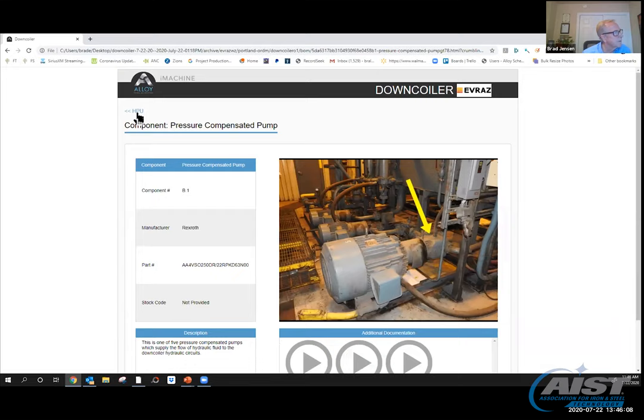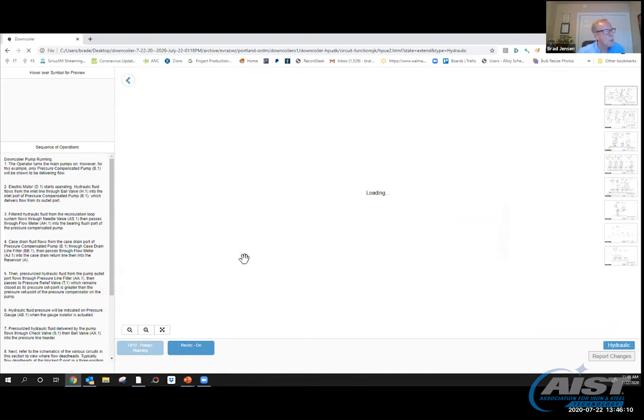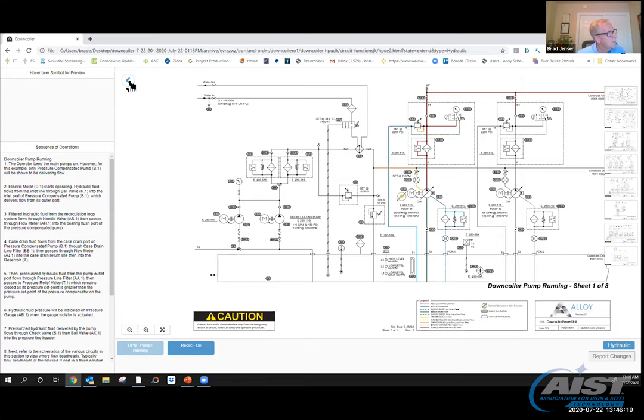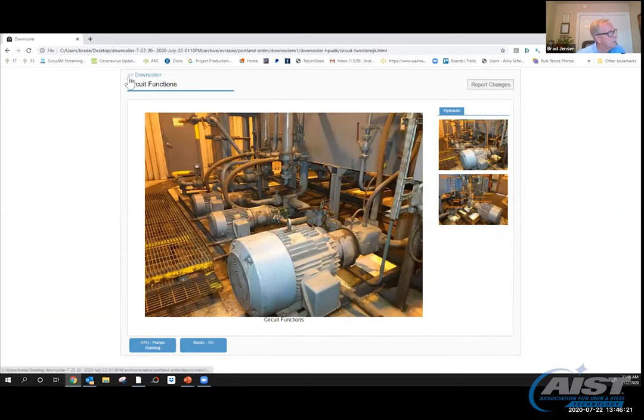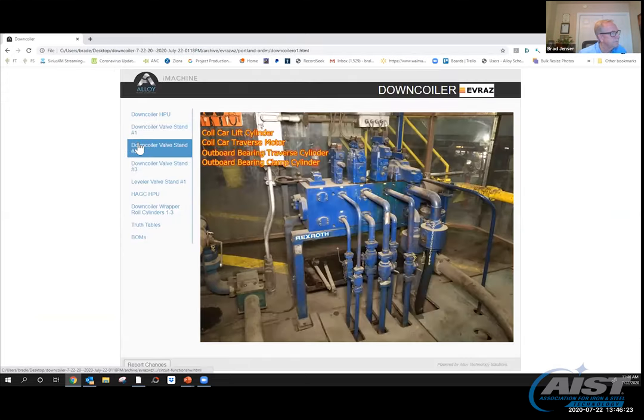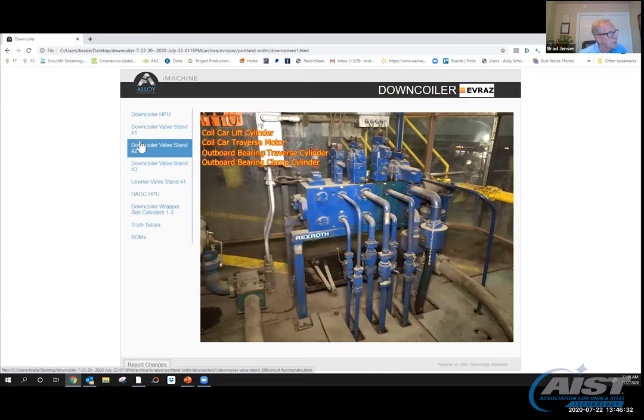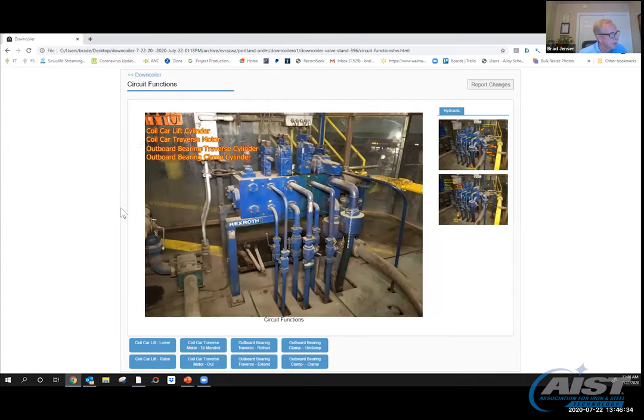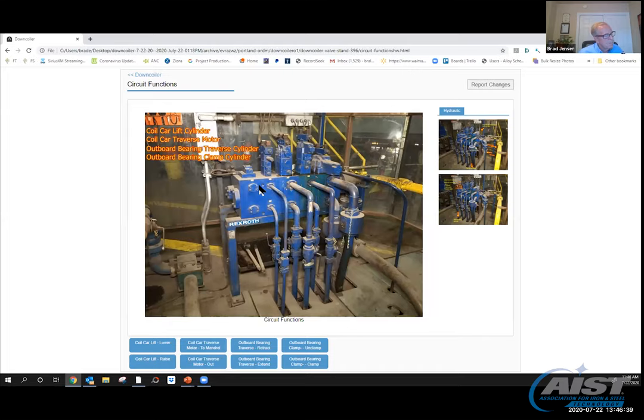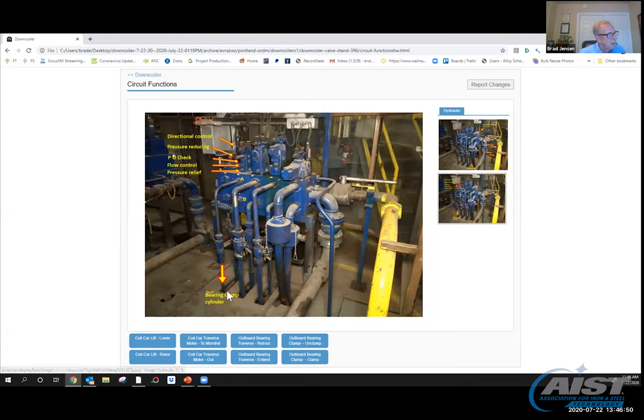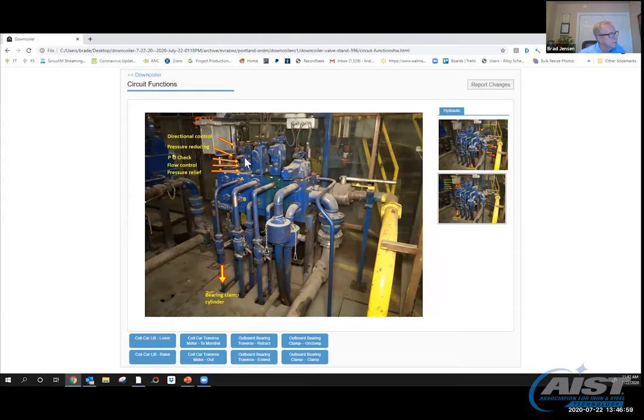A variable displacement pressure compensated pump is most often used in a closed center system. This example uses a pressure compensated piston pump. Understanding the functionality of a piston pump is helpful. If review is necessary, return to the piston pump section. What I'm going to do, because of the sake of time, we're going to continue downstream. We're going to go to valve stand number two and I'm going to take you to the outboard bearing clamp cylinder circuit. I'm going to click here. Now I have the valve stand—it's being fed from the hydraulic power unit. The ball valves that are opening and closing from the cylinders. I've got the stacks here. This is the one I'm going to zero in on.